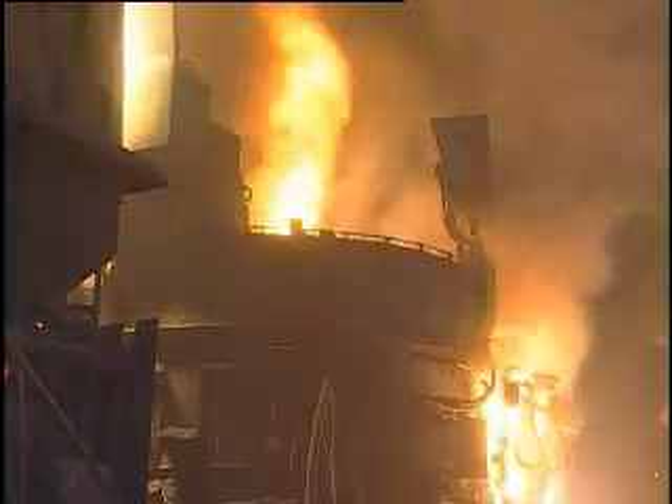The biggest benefit we received was our improvement in reducing holes in the furnace. We use RTDs to sense heat on the side of the furnace that can come either from an arc deflection, from an arc flare, or from blowback on our co-jets. We were able to characterize this much more accurately and come up with more sophisticated controls. This allowed us to do two things.